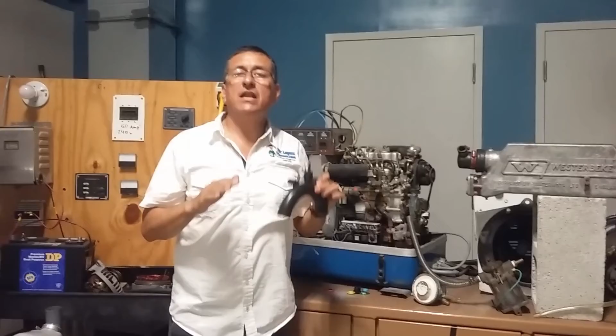The life of the generator depends on those anti-siphons. If those anti-siphons are not installed or improperly installed, immediately you start the generator, a couple of hours after the generator suctions water and the generator is destroyed.